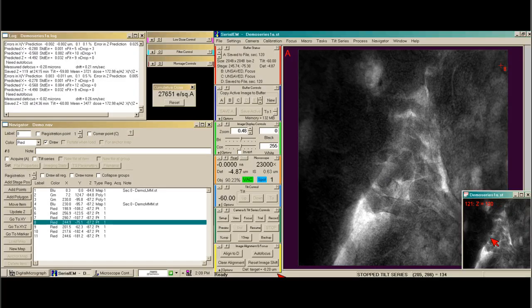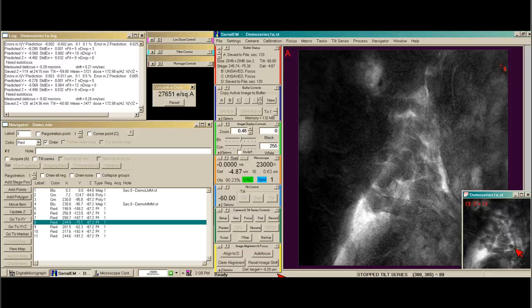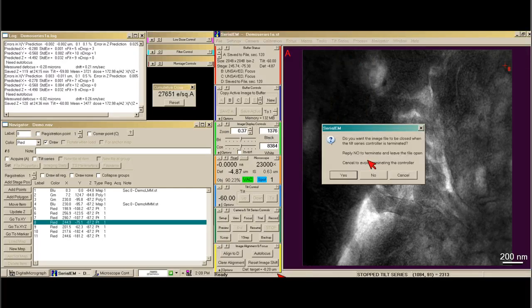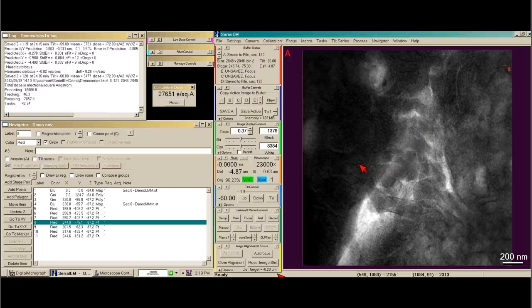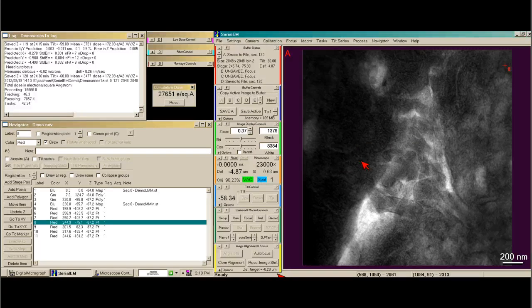I have this mini tilt series here in this little box and I can page through and see my tilt series from start to finish — it looks fine. Now I need to go to tilt series and terminate the tilt series — yes, I want to close it and completely terminate it. It wants to know if I want to save a zero tilt view in the buffers if I plan to rotate it right away, and I'll say yes. For safety, I always immediately go to zero degrees so that I don't forget and try either rotating the grid or moving the stage at high tilt.